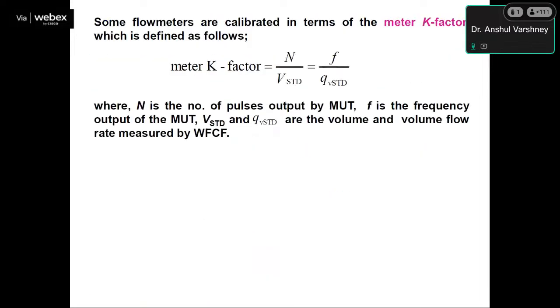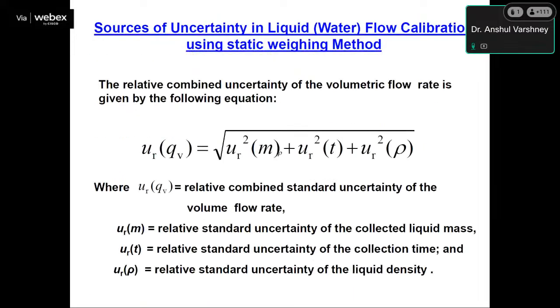These are the sources of uncertainty in water flow calibration using the weighing method, like the relative combined uncertainty of volume flow rate, and this is the uncertainty for collected liquid mass.